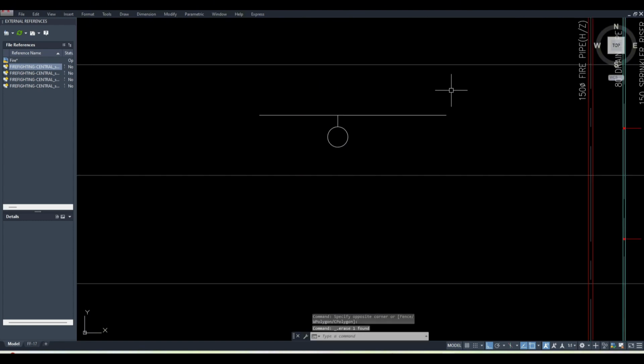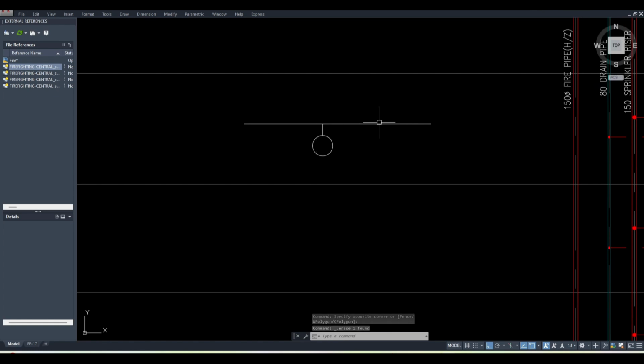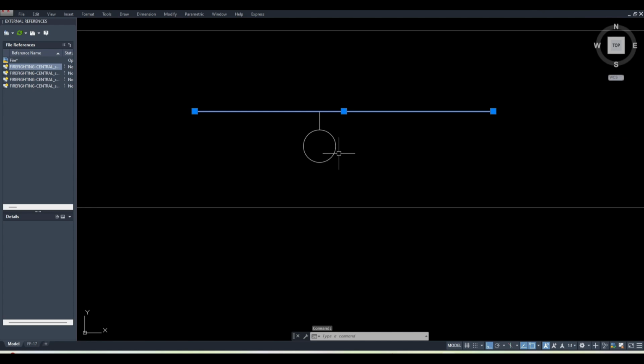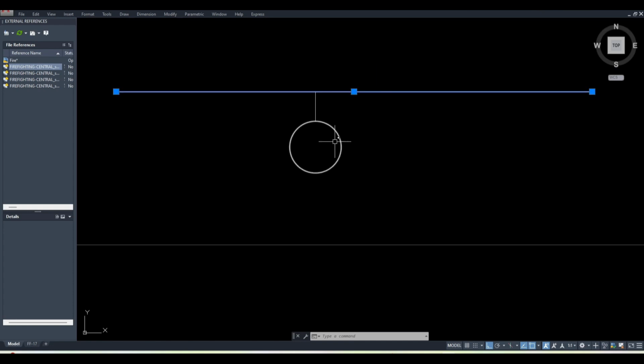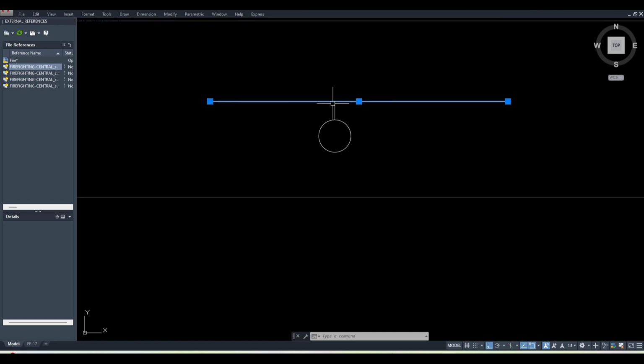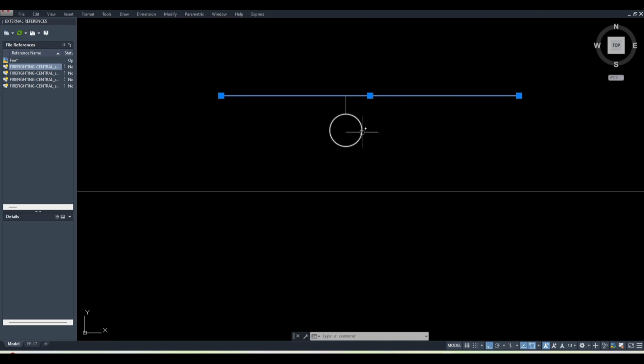First benefit, your drain can occur very easily, right? It can happen like, from here it can come to this, and then it can go back. Also, when you connect directly from here, then also drain can happen, but scaling forms. Since this water is dumped there for a long time, the scaling, like the debris, tends to collect in this bottom portion, which can obstruct the flow. So it is always advised, if you can take it from the top, the debris collects at the bottom, so that the chances of choke up of this pipe are less. So that's why we keep it on the top. There is no rule which says that you cannot connect like this, but this is the best practice.